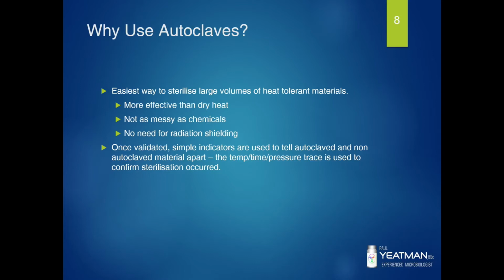The temperature and pressure trace, and also time trace from the autoclave cycle, is what you must look at to determine if your cycle is effective. And an inadequate autoclave cycle can still produce a change in the autoclave tape, as I said. Once the cycles have been approved, then the contents can be released for use. So here I recommend that you don't even open the autoclave until the traces have been confirmed and you've signed them off as approved, which effectively approves that equipment for use, and then you can remove it from the autoclave.